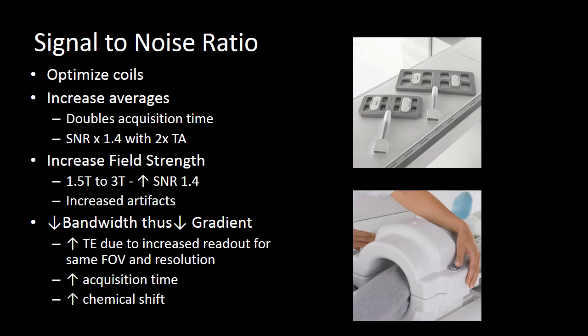You can also increase your field strength — that's why we develop higher field strength scanners, going from 1.5 to 3 tesla. You get an improvement in signal-to-noise ratio by 1.4, but you do increase the number of artifacts created at higher field strength. You can also decrease your bandwidth, which will decrease your gradient and improve your signal-to-noise ratio, but it causes increased chemical shift artifacts and increases your acquisition time.